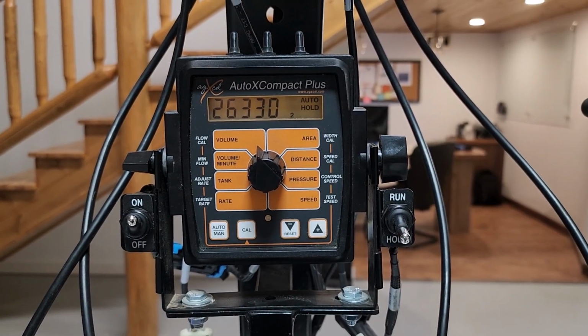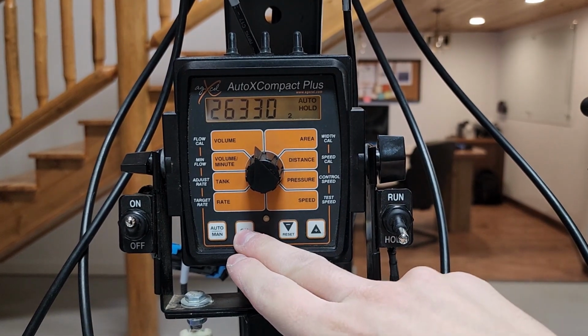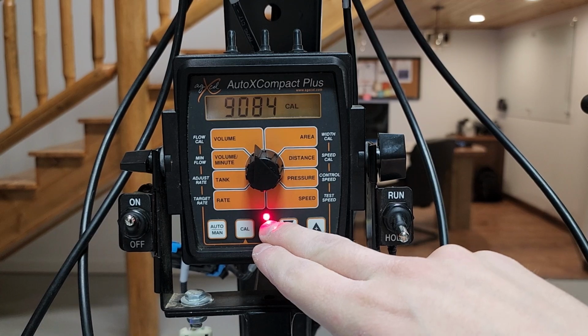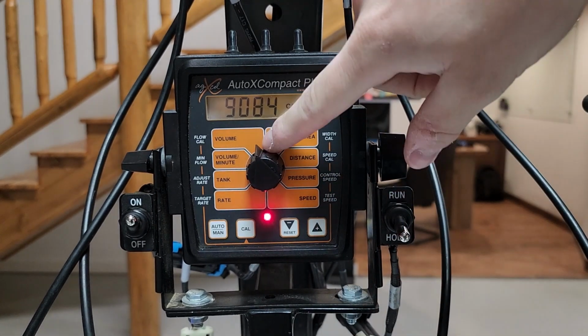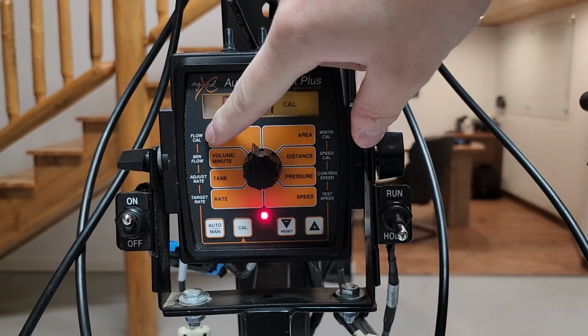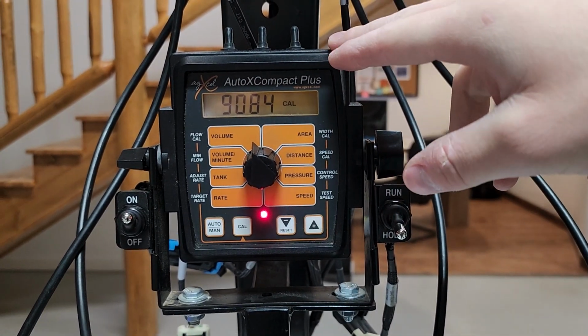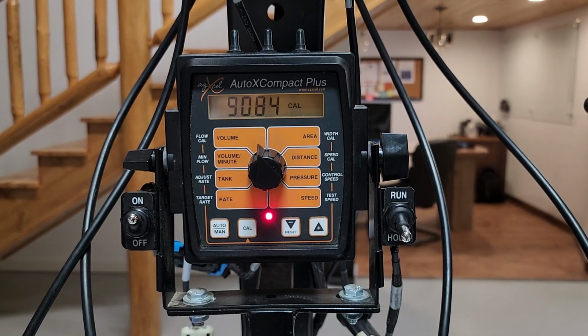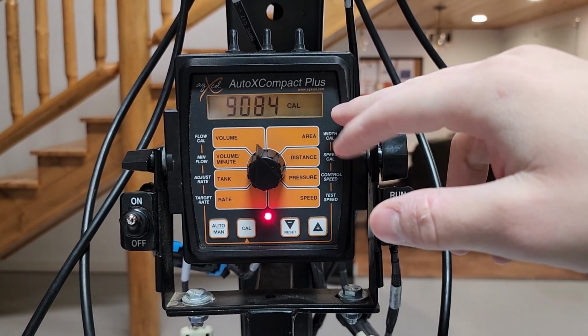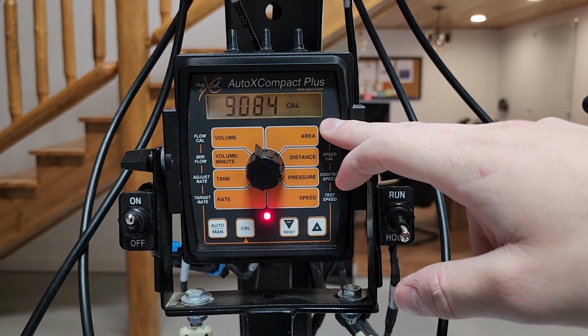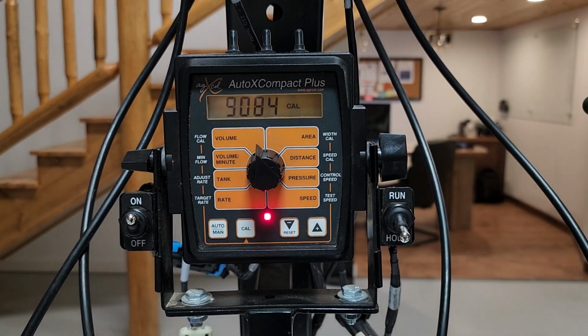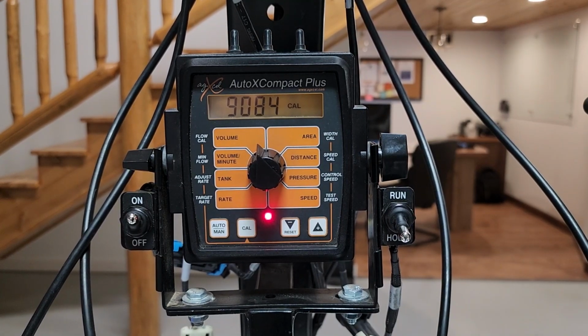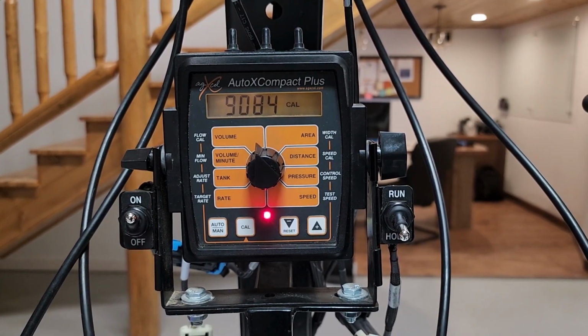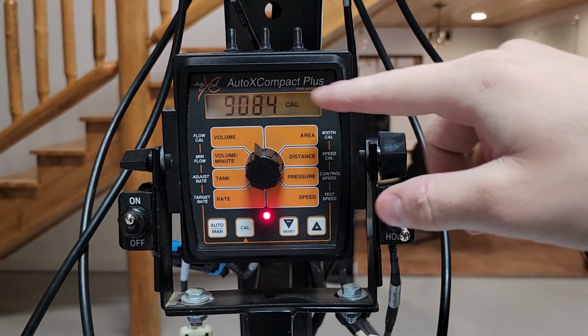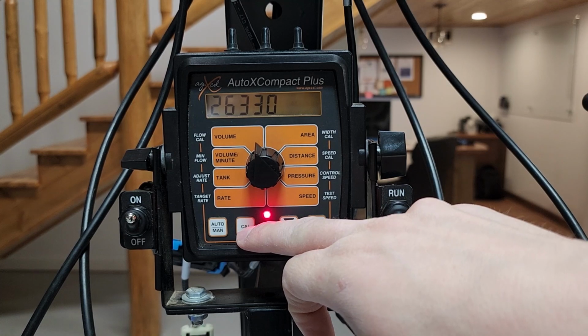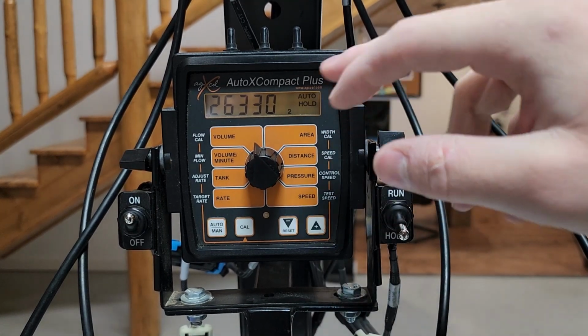And then looking at the AutoX controller, to go to your flow calibration, press and hold the cal button for about 3 seconds. Your red light turns on. That means you're in your settings mode. Turn your knob over to where it says flow calibration under volume. And for the AutoX controllers, whatever the pulses per gallon on your flow meter is stated as, you need to multiply it by 2, and that will be your flow calibration for your AutoX controller. So say if your pulses per gallon is 11355, multiply that by 2, and then your flow meter calibration would be 22710. Enter that. Once you enter your flow calibration number, press and hold the cal button for about 3 seconds. The red light shuts off. Then your setting will be saved.